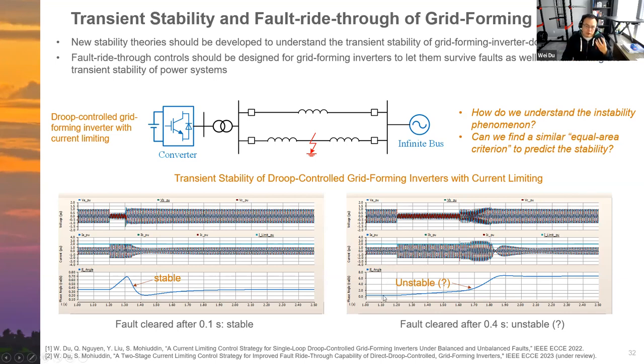So the grid forming inverter's phase angle loses synchronism with the grid during this transient. This is very similar to what you see in the synchronous machine, but there is still some difference. The key dynamics are basically governed by the droop control and the different current limiting algorithms. This tells us there are some fundamental things we should look at for a grid forming inverter dominated system, especially considering fault ride through and the transient stability.